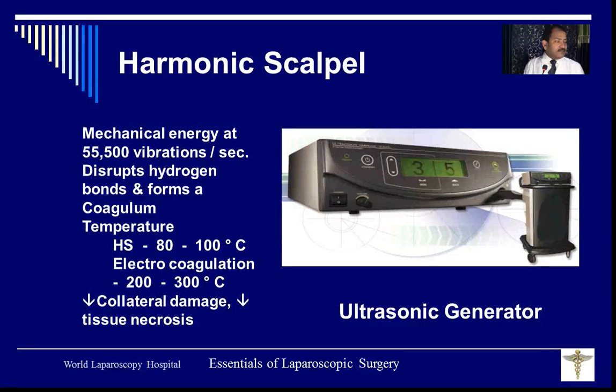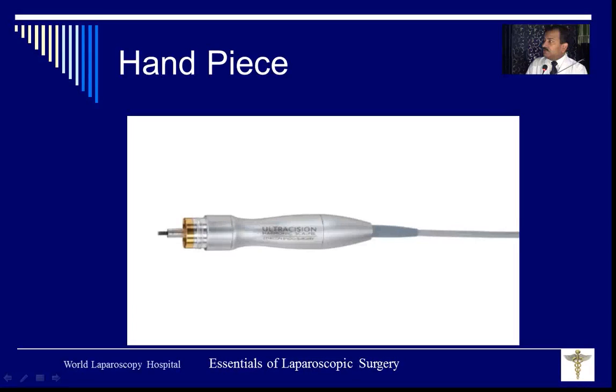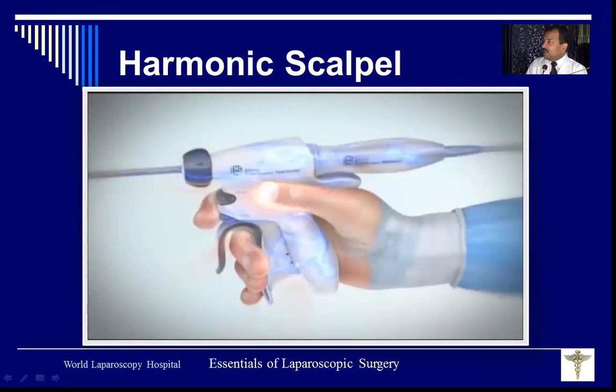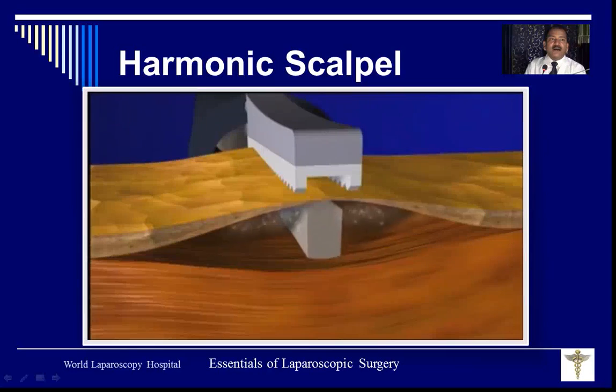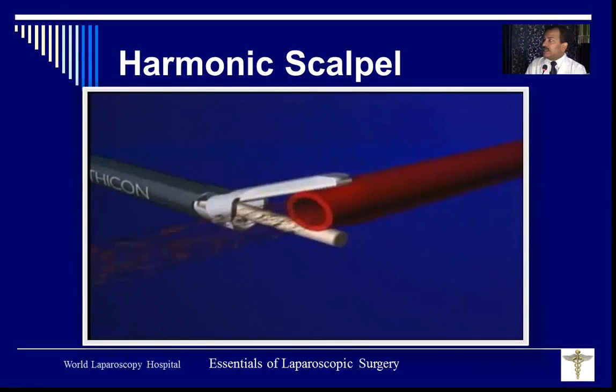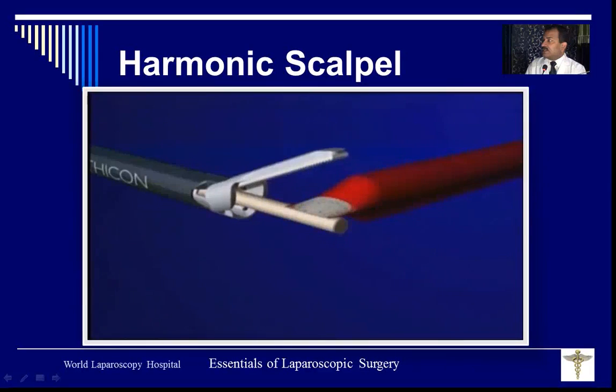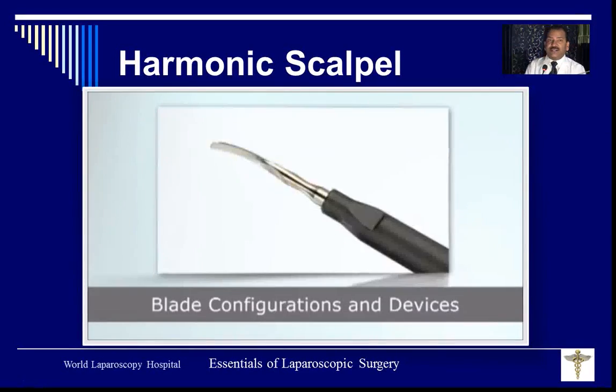And actually it vibrates. And I will show you how it vibrates and how it cuts and coagulates. And this way we will see it. So this is the minimum, this is similar concept, this is the maximum, and in this transducer you will attach it, and after that here this is minimum, this is maximum. This is in your finger, and once you touch it, it vibrates, and due to that vibration heat increases, and then it coagulates and it seals the vessel up to 5 mm.